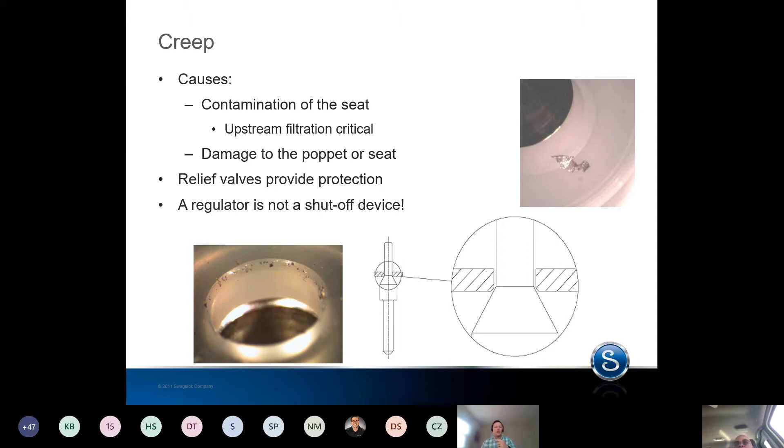Now, as it zips down the line, the space between the seat and the poppet is very small to create those pressure drops. So that burr is moving pretty fast and it's going to embed itself in that seat, right? Causing a small leak path that is between the poppet and the seat. And even if you get some extra closing force and maybe you have a higher inlet pressure, you still might not be able to fully seal and you'll see creep.